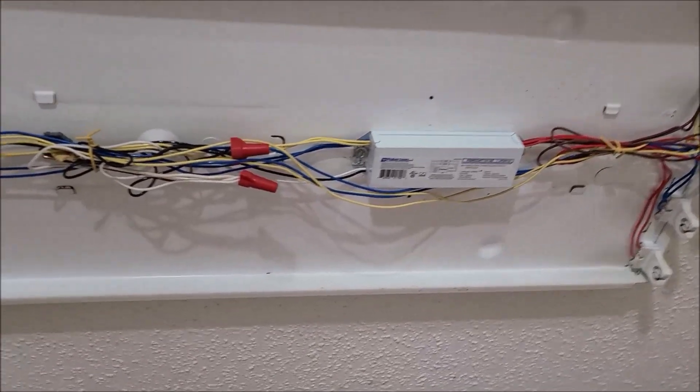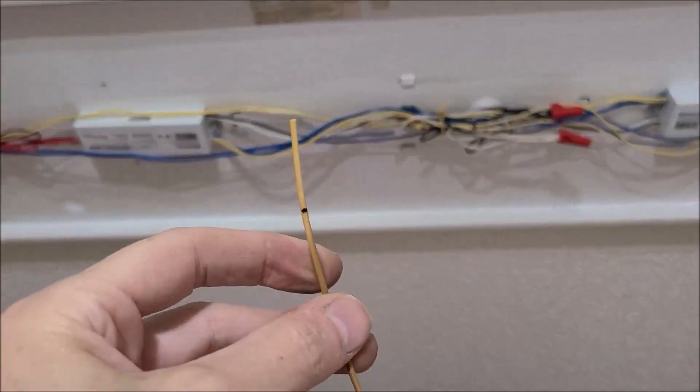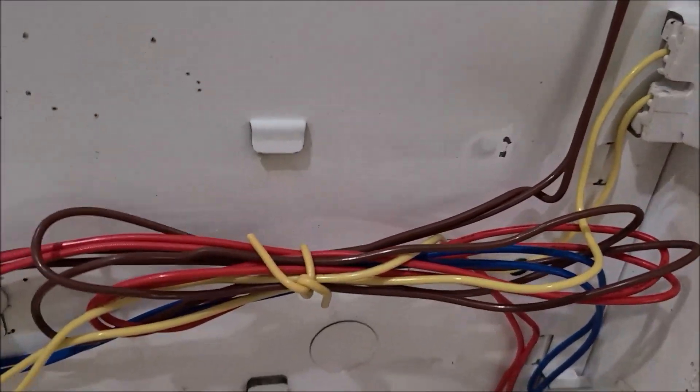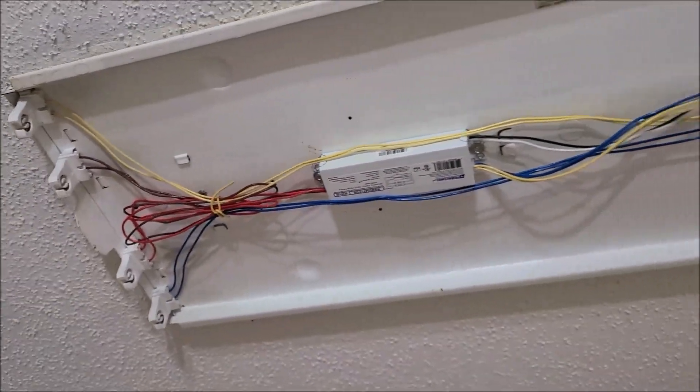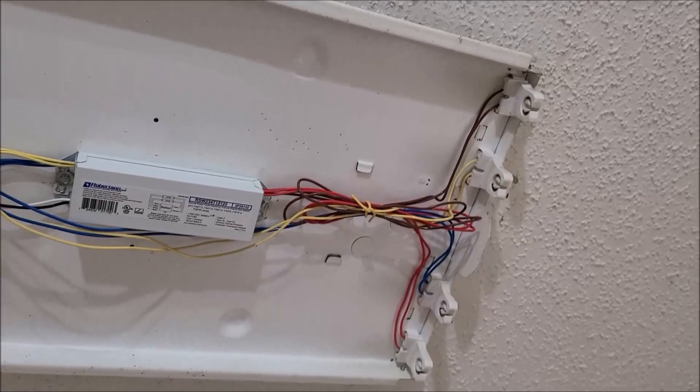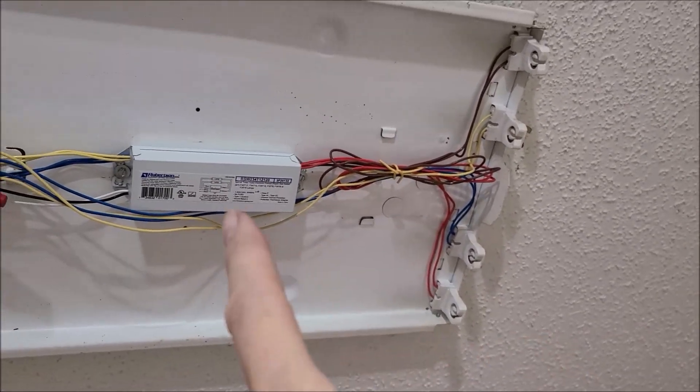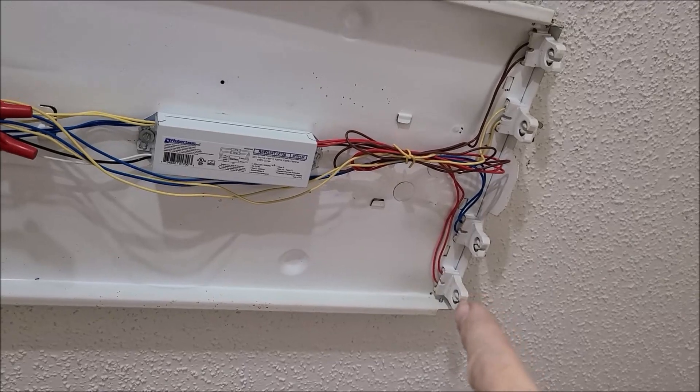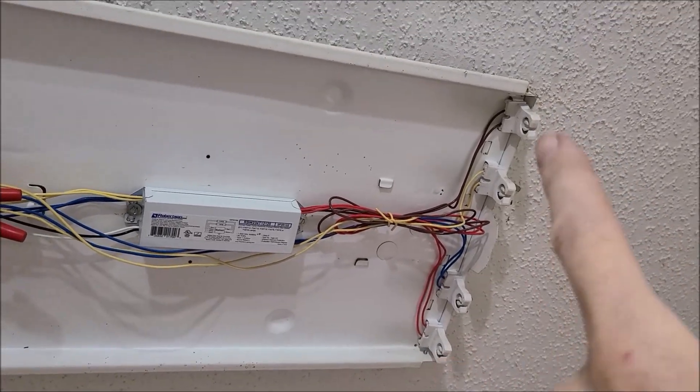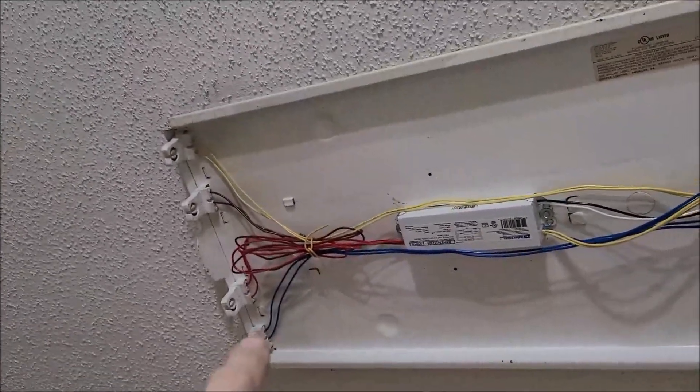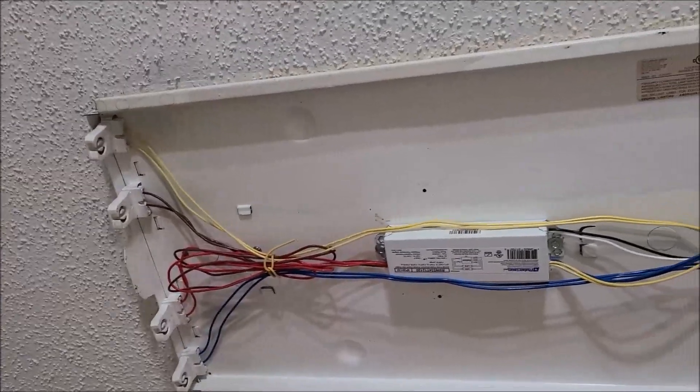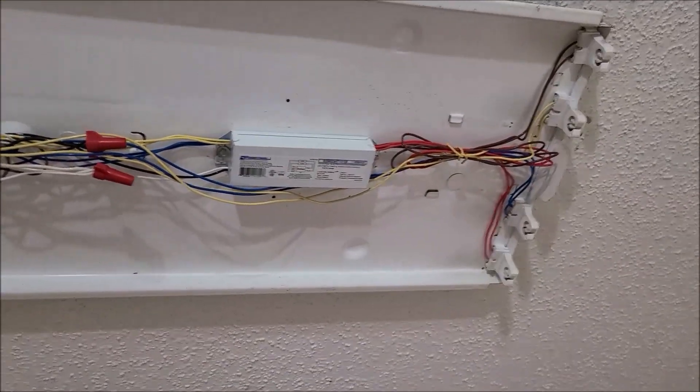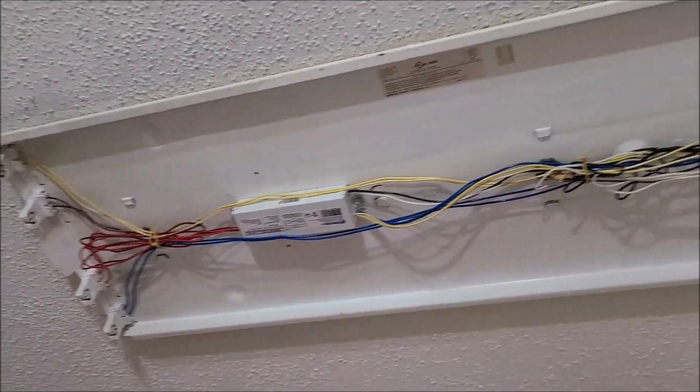Well, you see I got my wires all tidied up nice and neat. I just see, because I had all this leftover wire, I cut me a couple pieces off, kind of tied them up there so they're not hanging down in a way. But easy peasy. So you can kind of look at this, look at your fixture and just wire, you just look at your colors. Remember, this ballast powers the two outer bulbs, this socket and that socket. So got red and then brown. Then on the other side, once again, the two outer sockets, you got your blue, got your yellow. Just do the same thing like I did and it'll work just fine, no problems at all.